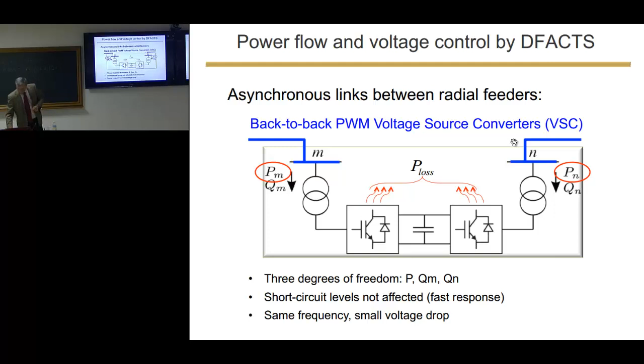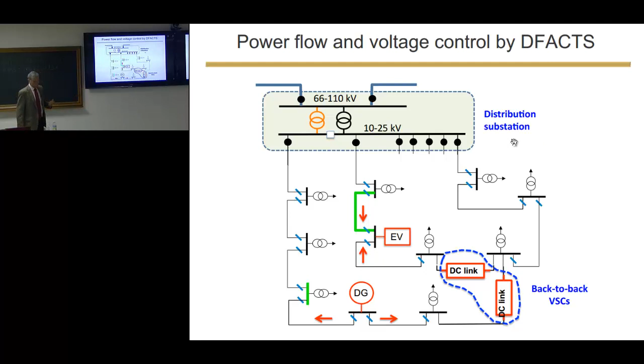And this can be used, for instance, consider this example. There was an overvoltage here because of excessive injection. There was a congestion here because of excessive consumption of fast-charging electric vehicles. If we use this link here, which is a way of asynchronously and flexibly linking, closing the loops, it's a flexible loop, so to say, we can move energy of this generator through this side and it can be used for charging the vehicles. So we could eliminate the congestion and we could eliminate the overvoltage because of this DC link, asynchronous link. Okay, so this is an idea that we have already tested in the lab and is working, and we have simulated, of course.